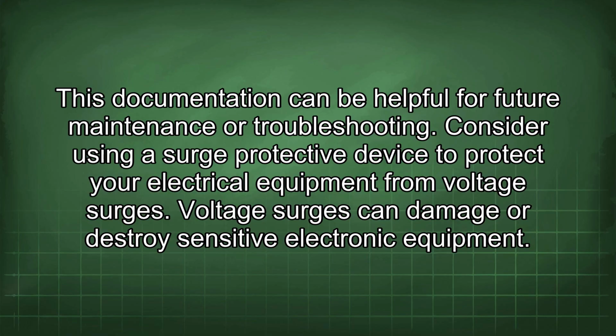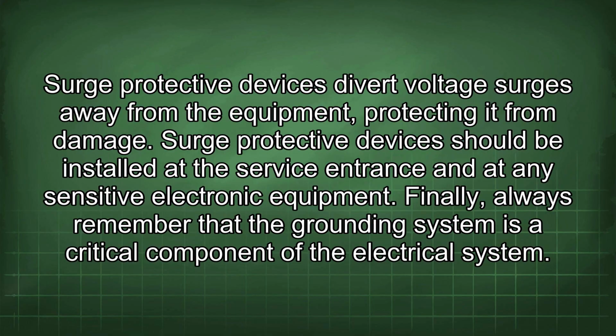Consider using a surge protective device to protect your electrical equipment from voltage surges. Voltage surges can damage or destroy sensitive electronic equipment. Surge protective devices divert voltage surges away from the equipment, protecting it from damage. Surge protective devices should be installed at the service entrance and at any sensitive electronic equipment.